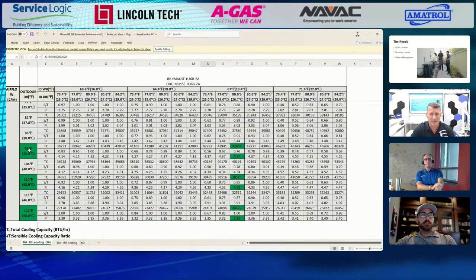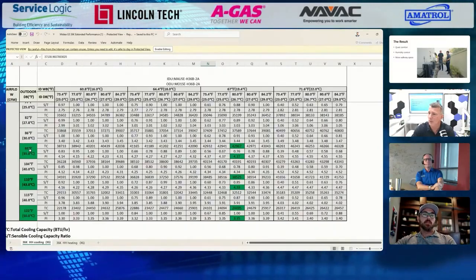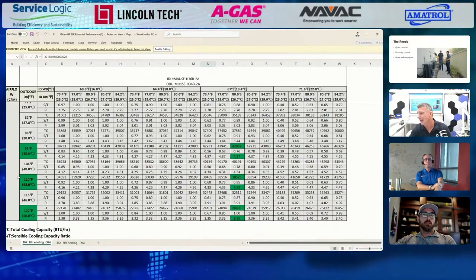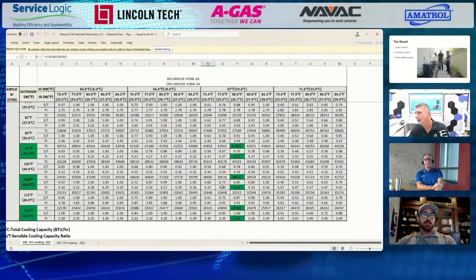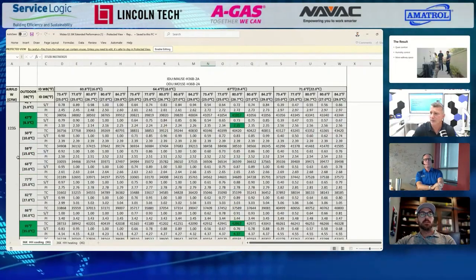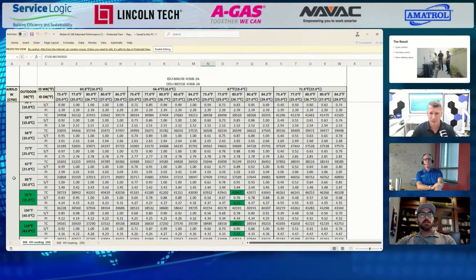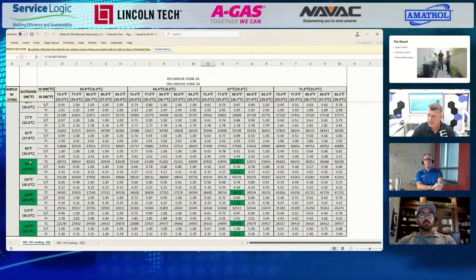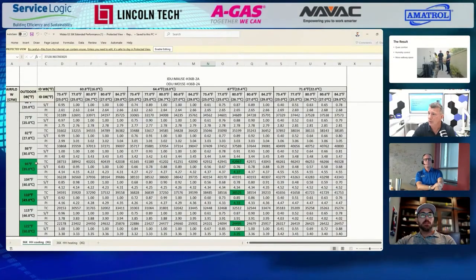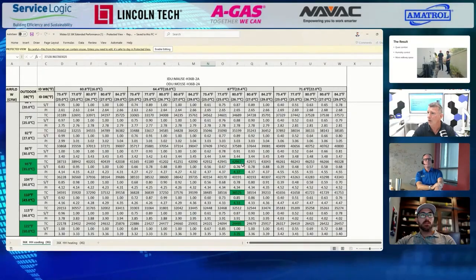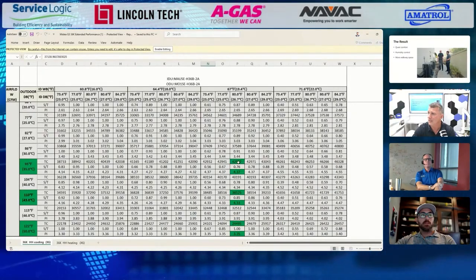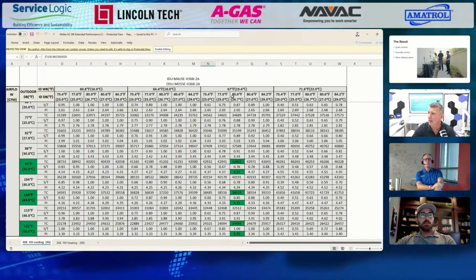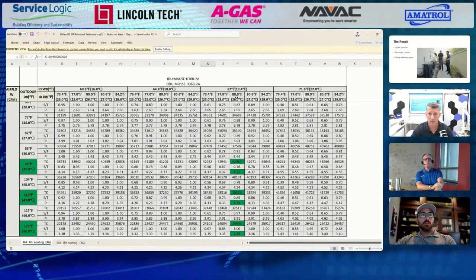We spend half of a chapter diving into data tables to understand what the actual capability is. So let's look at that 95-degree range. In this particular one, my airflow is 1,235 CFM, pretty realistic for these 3-ton units that you would be operating. At 95 degrees, now this is outdoor dry bulb, right? And we look at design on this particular one: indoor wet bulb 67 degrees, indoor dry bulb 80, all right? So that's a pretty realistic day.